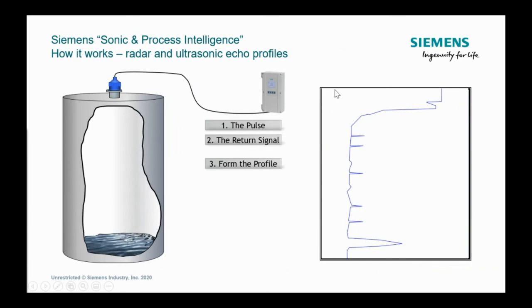Okay. So as we're looking down the page here, our vertical axis is showing distance from the face of the transducer going down, and moving to the right is showing magnitude or intensity. So here at the zero level, I have a ring down to the noise floor, and at some distance, I get a big echo off of the material. We're going to take this echo profile and rotate it 90 degrees. Some people like to look at it this way simply because it's showing visually down the page, like down the tank.